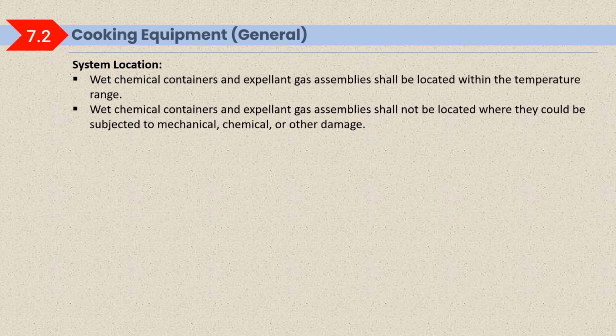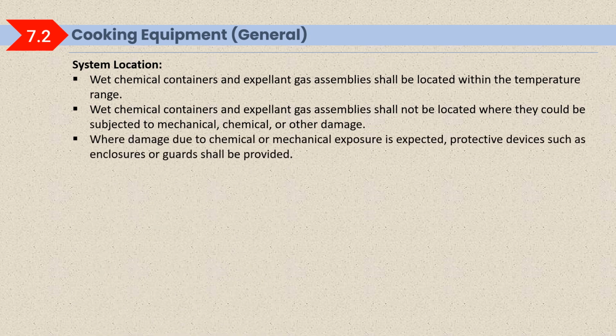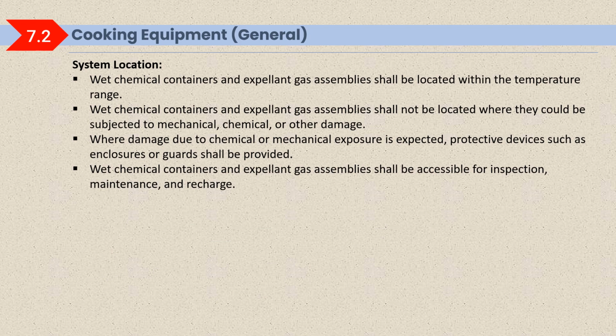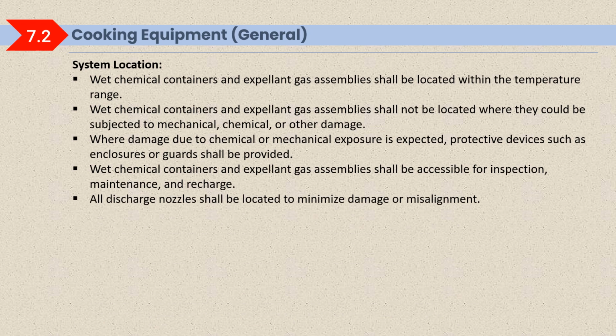Wet chemical container and expellant gas assembly shall not be located where they could be subjected to mechanical, chemical or other damage. Where damage due to chemical or mechanical exposure is expected, protective devices such as enclosures or guards shall be provided. Wet chemical container and expellant gas assembly shall be accessible for inspection, maintenance and recharge. All discharge nozzles shall be located to minimize damage or misalignment.